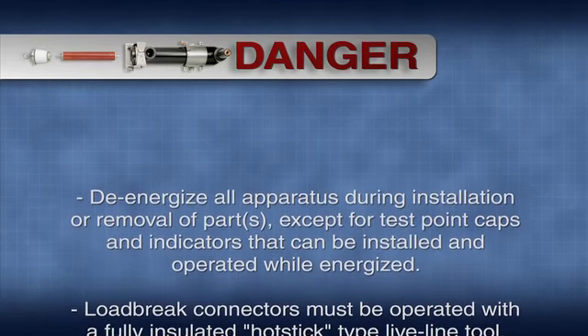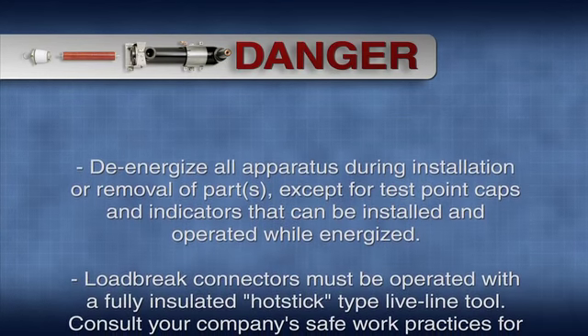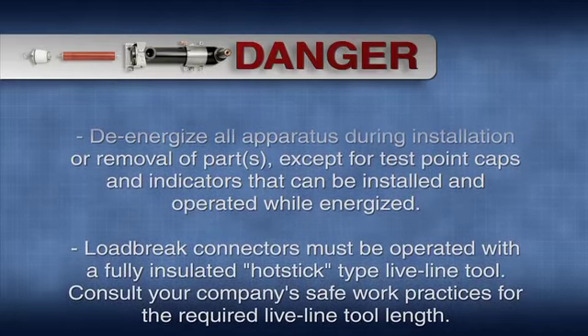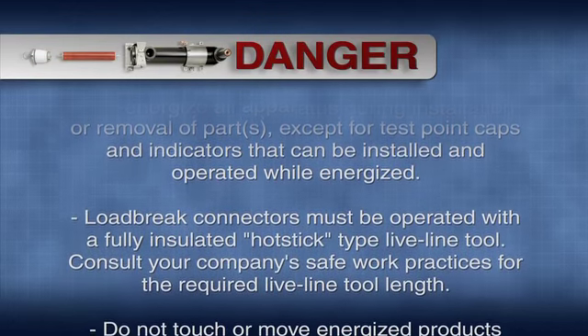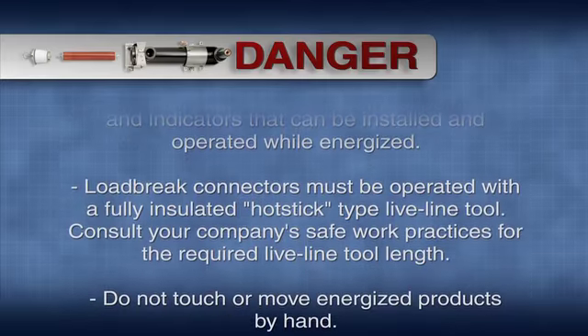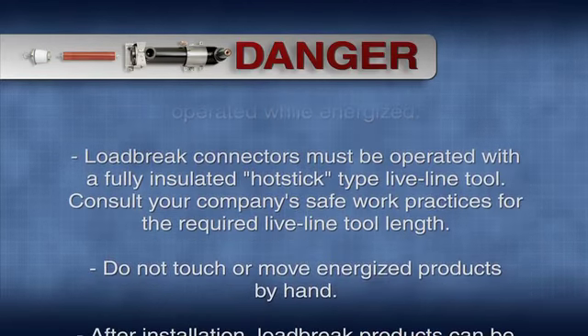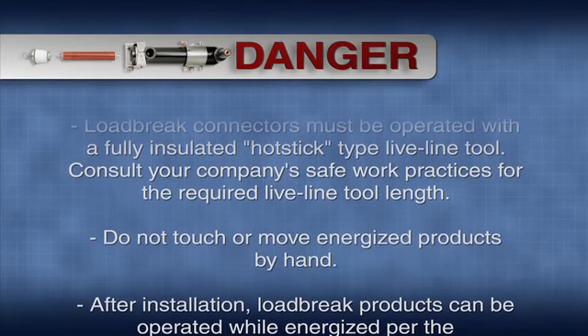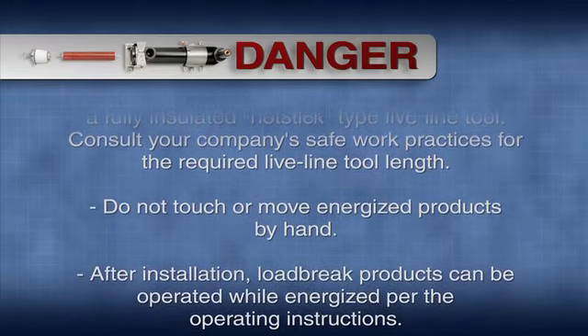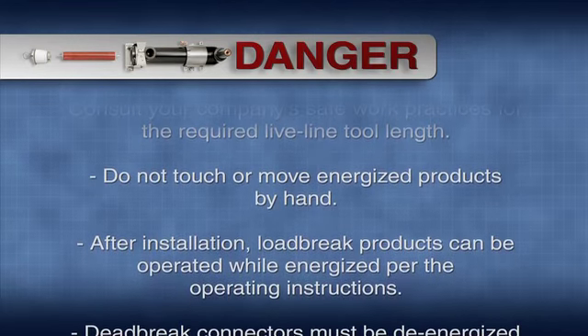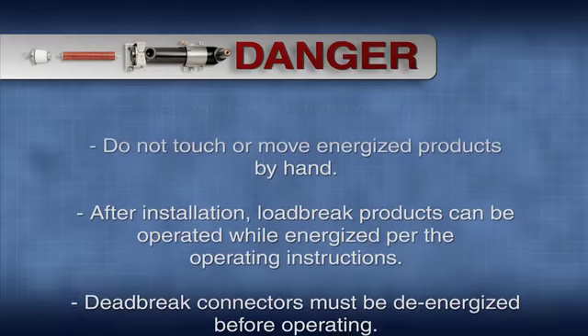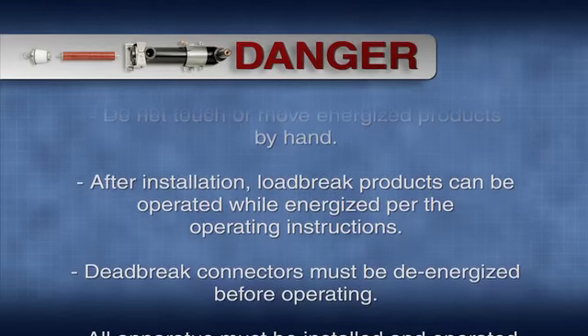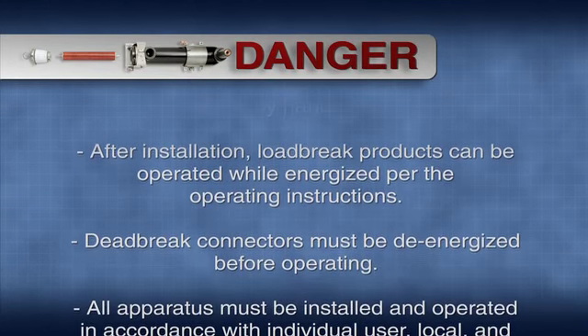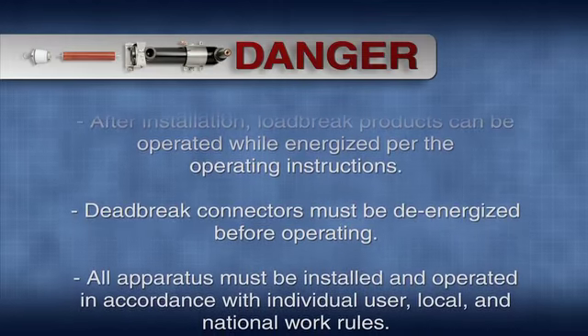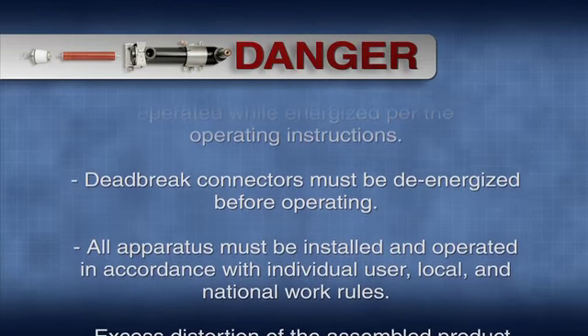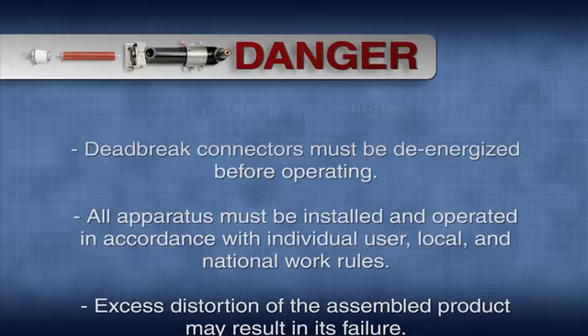All apparatus must be de-energized during installation or removal of parts, except for test point caps and indicators that can be installed and operated while energized. Load break connectors must be operated with a fully insulated hot stick type live line tool. Consult your company's safe work practices for the required live line tool length. Do not touch or move energized products by hand. After installation, load break products can be operated while energized per the operating instructions. All dead break connectors must be de-energized before operating.